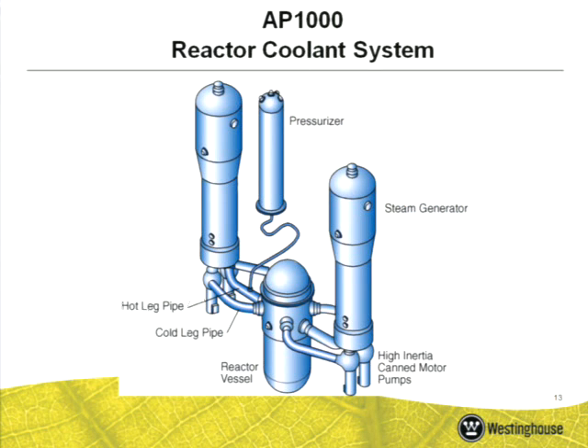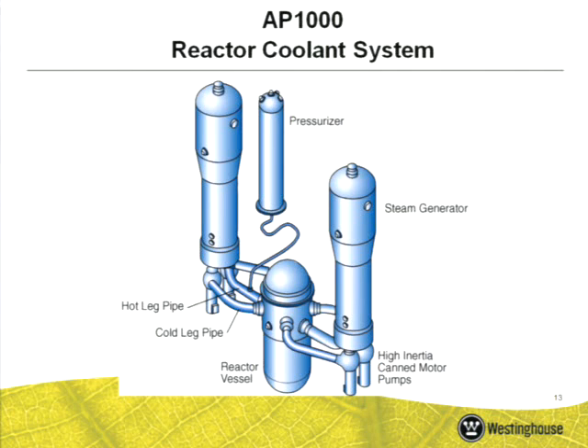So the reactor coolant system for AP1000 is basically what we call a 2-loop reactor coolant system. There's a primary water circuit and a secondary water circuit in pressurized water reactors. The primary water circuit goes through the core, gets heated up, goes through a heat exchanger, transfers the heat to a secondary water circuit, which boils the water, turns it into steam. The steam goes to a turbine, is condensed, and returned to the steam generator to be boiled again. So there's 2 circuits, and this shows the primary circuit.